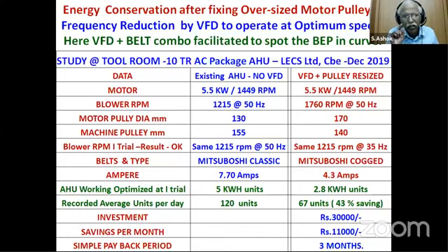You can concentrate on any of your air conditioning installations. AHUs can be brought down by 20 to 30% minimum to suit the best efficiency point in the performance curve. Ultimately, this is achievable and the payback is simple. Payback is within 3 months. Cost is just 30,000 and per month the return is almost 10,000, so the return on investment is 3 months.